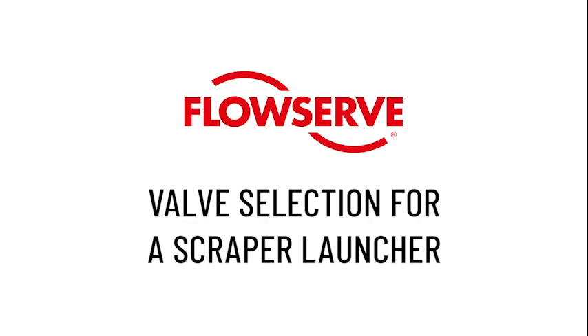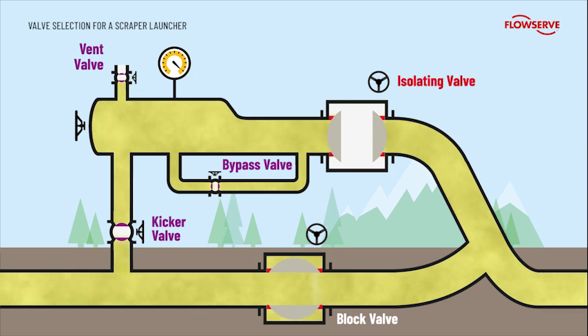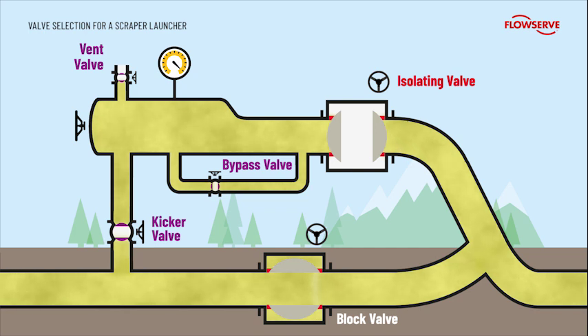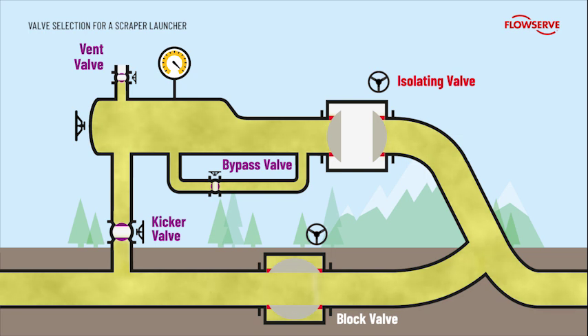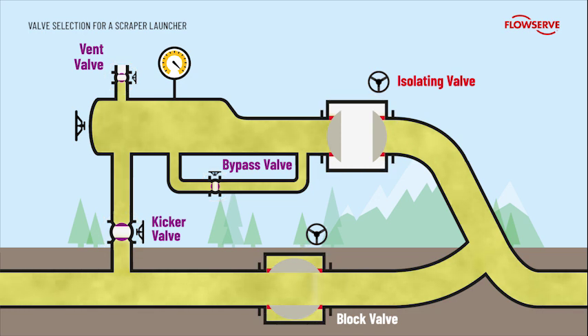Valve selection for a scraper launcher. In order to clean a pipeline, a scraper is passed through the pipe to remove any scale or debris. The scraper is launched into the pipe using gas pressure via a launcher and removed via a receiver. Launchers and receivers are similar in design and operating sequence, and both use a series of valves to control the gas flow. In this video, we will show a typical launcher sequence to understand what the roles and critical requirements of each valve are, so an optimal valve selection can be made.